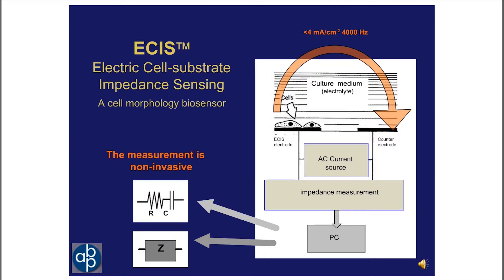But, of course, this is an AC circuit. Impedance represented by the letter Z is measured in ohms. Our more sophisticated instruments, in addition to monitoring the voltage across the electrodes, follow the phase difference between the current and the voltage as it oscillates back and forth. And from this information, we can describe the complex impedance, which we represent here as a resistor and capacitor in series. And so the output of the ECIS system will either be the impedance, measured in ohms, or the resistive portion of the impedance, again measured in ohms, or the capacitance of these gold electrodes, which will be in the range of nanofarads.